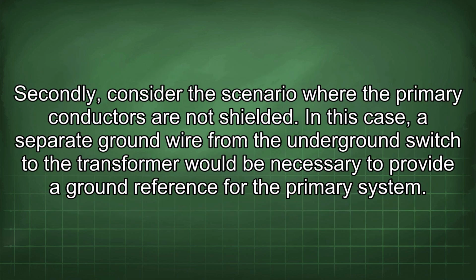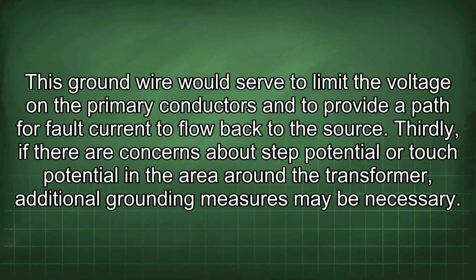Secondly, consider the scenario where the primary conductors are not shielded. In this case, a separate ground wire from the underground switch to the transformer would be necessary to provide a ground reference for the primary system. This ground wire would serve to limit the voltage on the primary conductors and to provide a path for fault current to flow back to the source. Thirdly, if there are concerns about step potential or touch potential in the area around the transformer, additional grounding measures may be necessary.